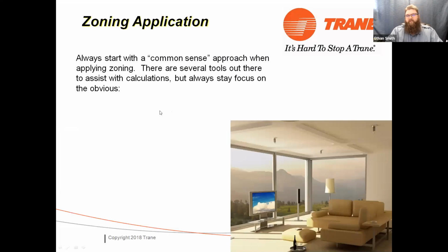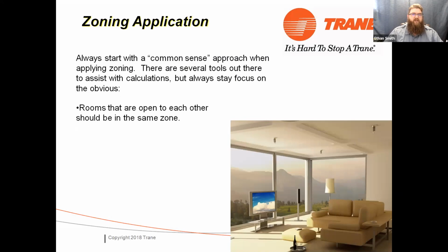So we talk about general rules. So here's your general rules for zoning. The first is rooms that are open to each other should be in the same zone. If you do not have a partition between rooms, like you see here, we've got a big living room. It's probably attached to a kitchen and a dining room of some variety. We'll show you an example house here in a minute that's got some common spaces. Common spaces should be tied to the same zone. If you have common spaces with multiple zones servicing them, you'll never be comfortable in them, period.